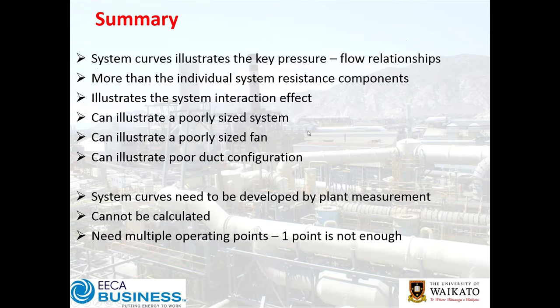In summary: system curves illustrate key pressure-flow relationships. They go beyond just individual system component resistance — they can illustrate system interaction effects, poorly sized fans, and poor duct configuration. They need to be developed with good plant measurements rather than theoretical calculation, and importantly, one measurement point is not going to be enough.